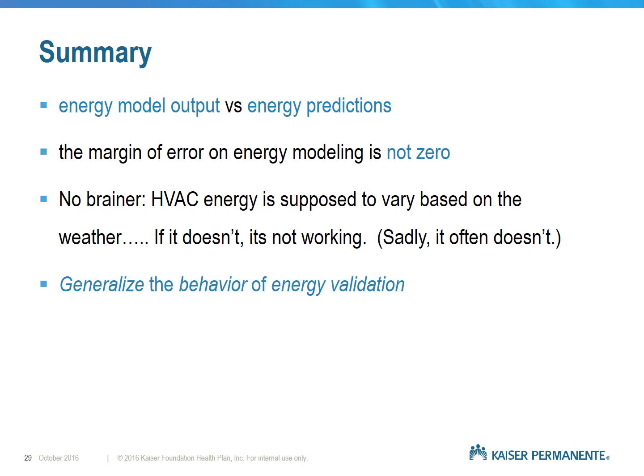And we talked about this - it's kind of a kindergarten concept, really simple: when it's hot outside, we should be using more cooling and more fan energy; when it's cold outside, we should be using more natural gas, less cooling, less fan energy. When it's 68 degrees outside, we should be minimized on both. It's pretty simple, but it is not easy.